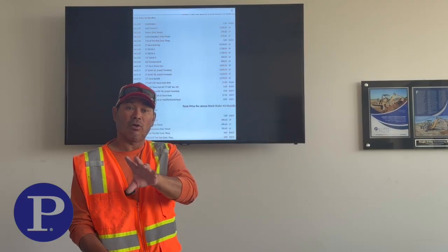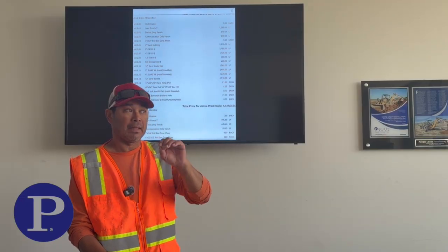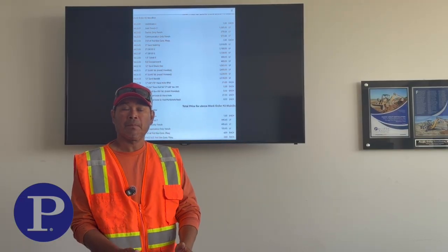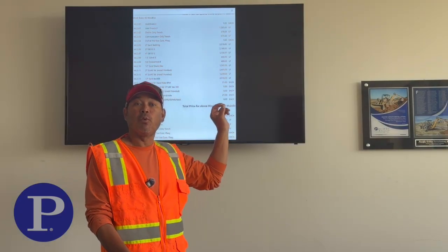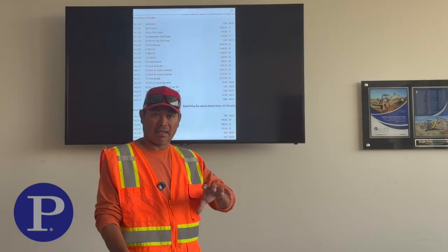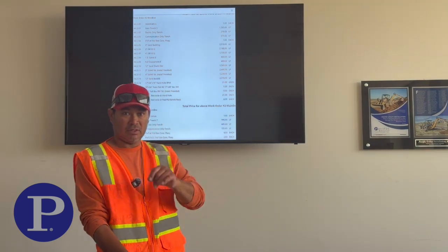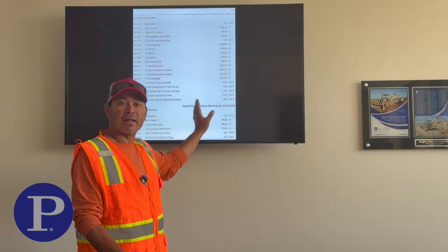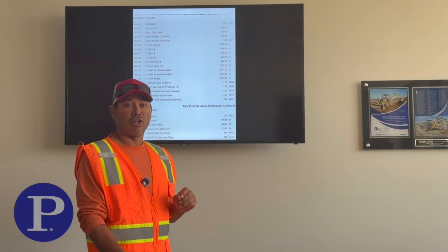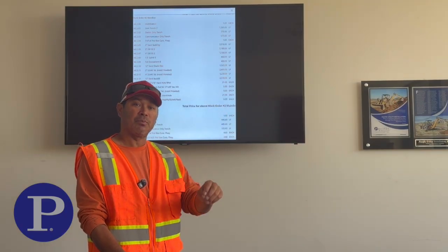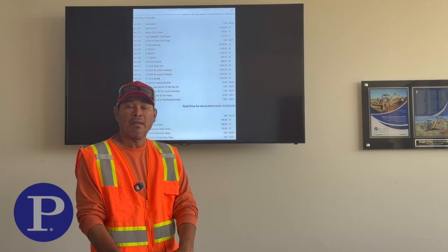So it changes on Edison, but if you go to Indio, for example, you put the two ground rods, but you weld it. You cad weld, not clamps. Another good thing, for Edison, the ground rods are 8 foot long. For Indio, they are 10 foot long. So it's something that we need to take into consideration too.